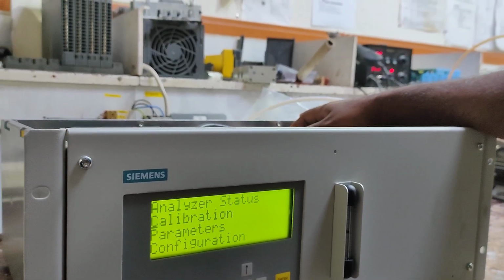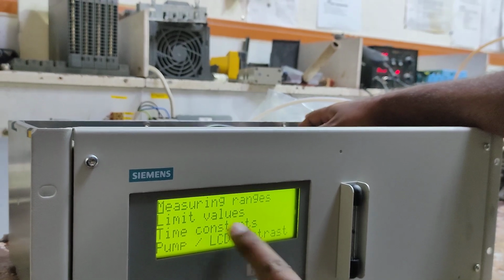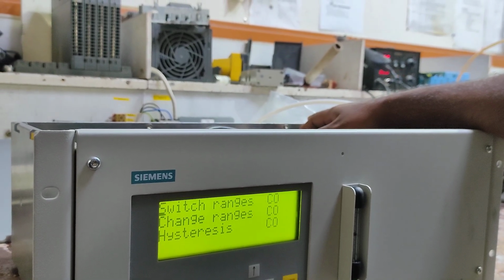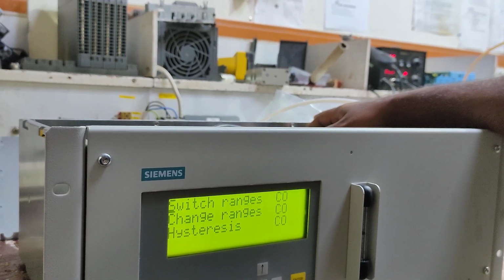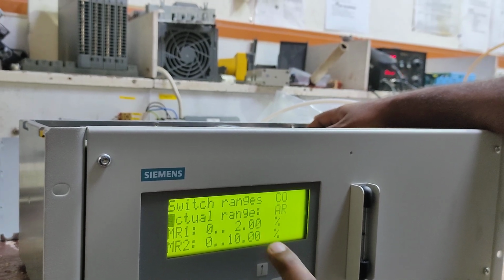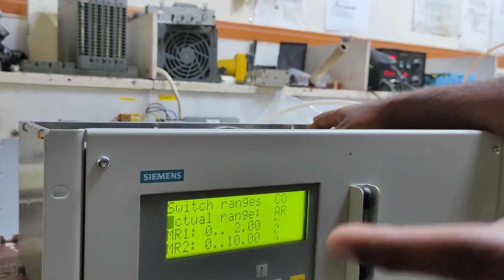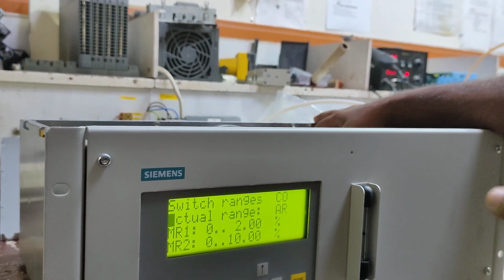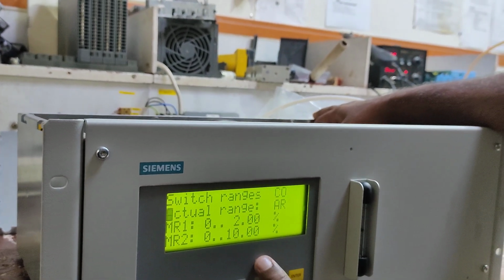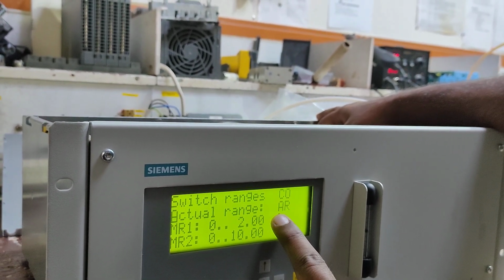Before going for calibration, we'll see the parameters. What is the measuring range? Here you can see the range for CO. It is a switching range. It should not be automatic. You have to select any one range, so your loop current will be stable. So what is your actual range now?